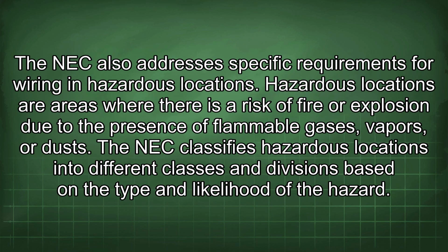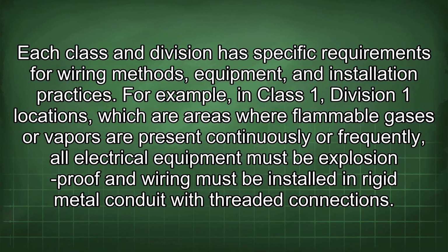The NEC also addresses specific requirements for wiring in hazardous locations. Hazardous locations are areas where there is a risk of fire or explosion due to the presence of flammable gases, vapors, or dusts. The NEC classifies hazardous locations into different classes and divisions based on the type and likelihood of the hazard. Each class and division has specific requirements for wiring methods, equipment, and installation practices.